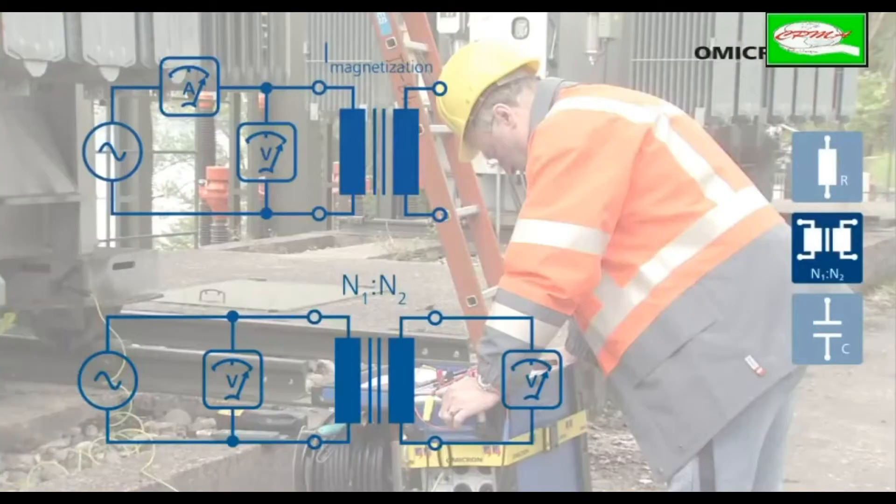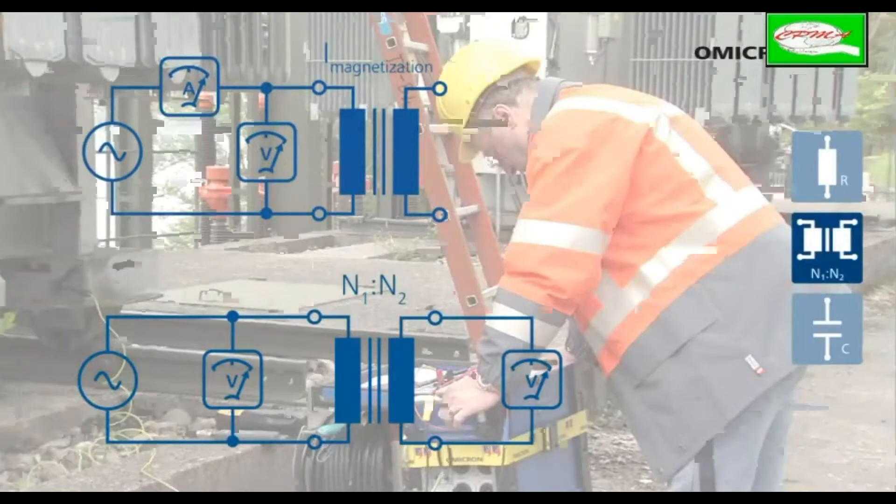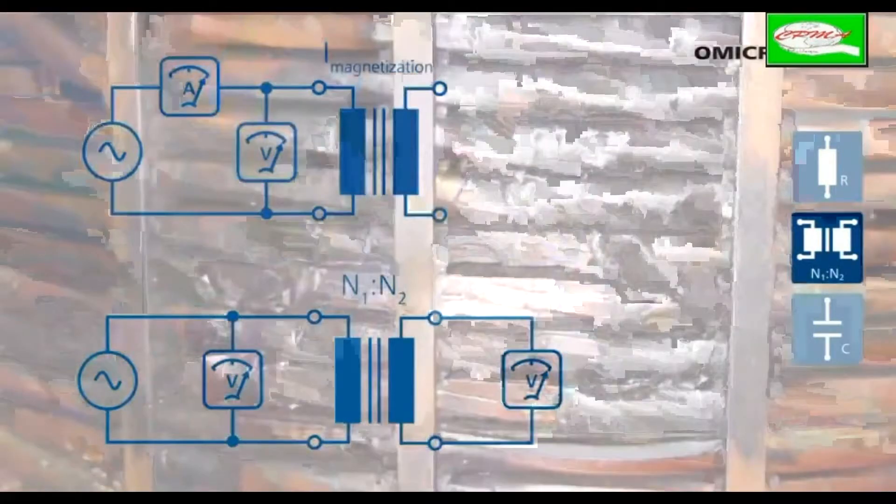Medir a relação e corrente de magnetização ajuda a identificar curtos circuitos entre espiras do enrolamento.